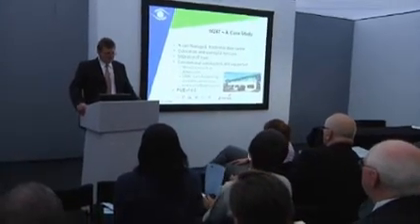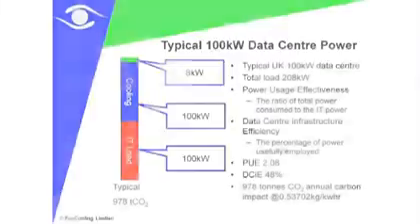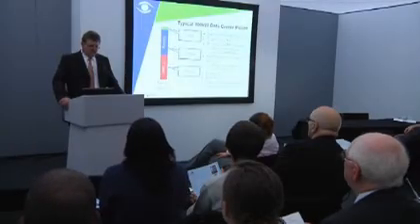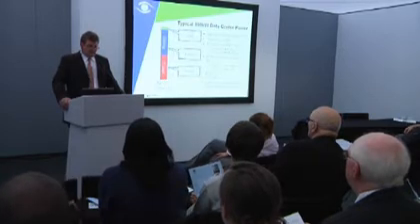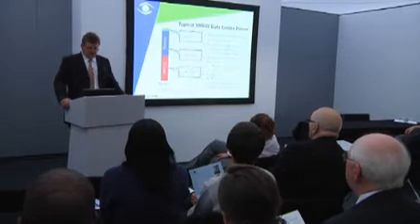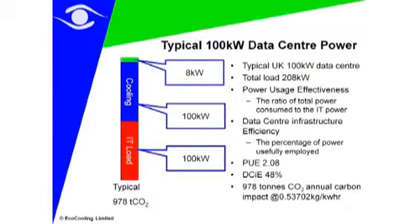What we call a PUE, a power utilization effectiveness. Now, what do we mean by PUE? Very, very important concept. We look at the efficiency of a data center and its energy use, or a server room, by looking at the ratio between the total energy used against what's really useful work done in the IT equipment. Now, many data centers in Britain run at a PUE of anything up to 2.5.